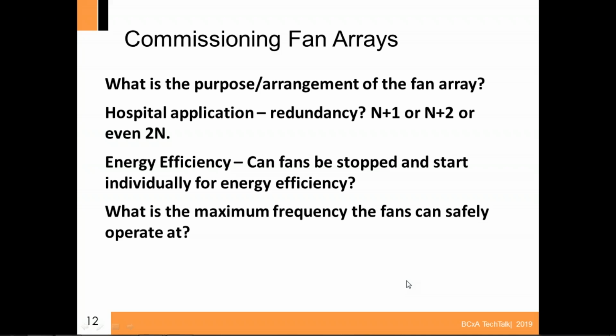They can get stuck open. And when we talk about testing here, you can have a problem with your maintenance personnel if they don't understand how to operate them, like how to shut them down and how to restart them. And what I've seen before is the fan spinning backwards and somebody try to kick an overload back on, or try to kick something back on when that motor, the three-phase motor, is spinning the wrong direction. The application of brakes on the VFD is great, but if the VFD fails, it doesn't really do you much good. So I hope that answered the question.